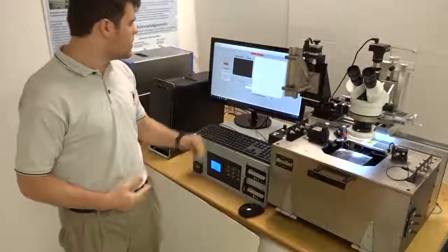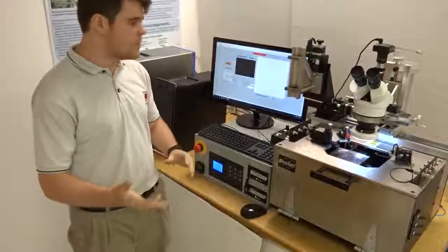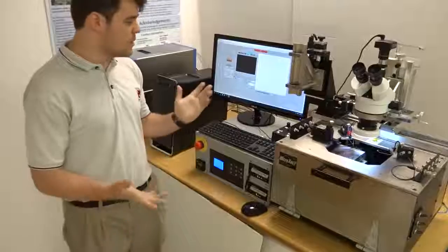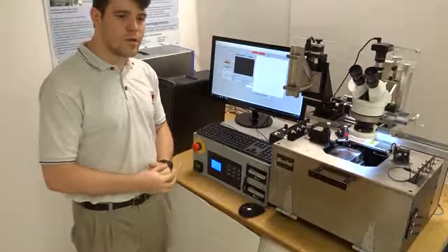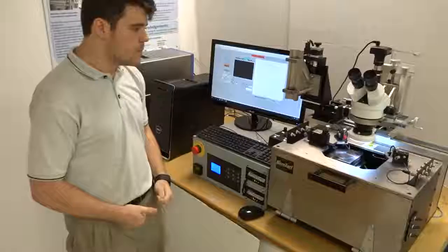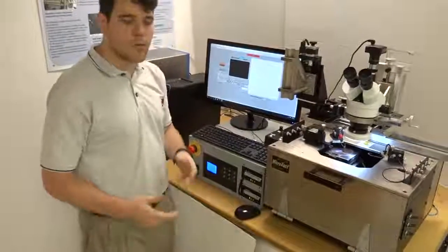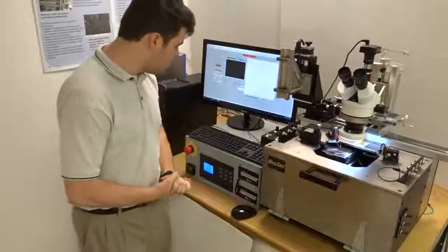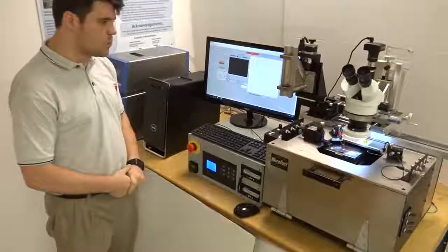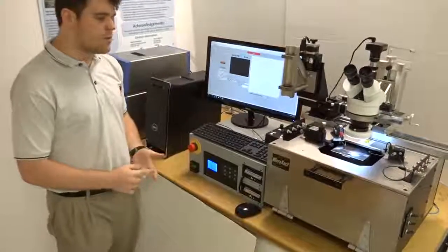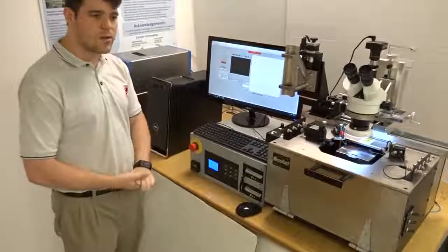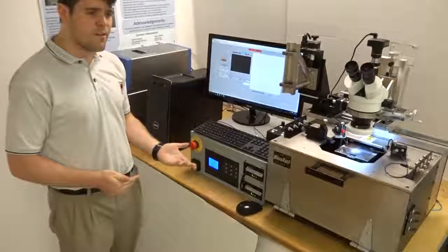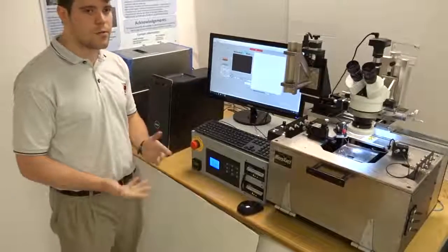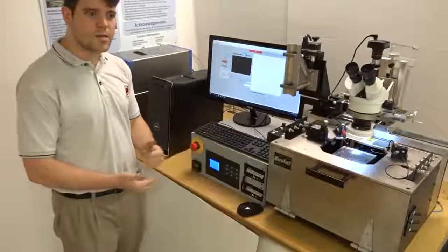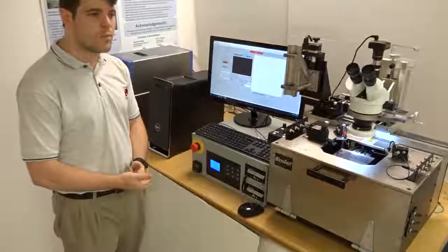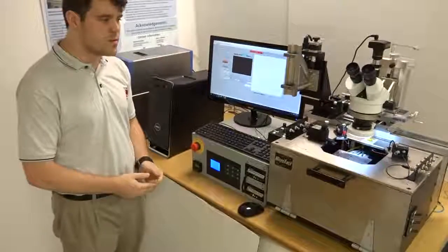We have a camera here that will feed us a high-definition video of what's currently happening, and it will then be able to show us the actual image that we see through this camera. While this is going on, a user can prepare their slides or move whatever they'd like to set up. This control box down here is responsible for ensuring the temperature of our thermal chuck, which can go, in this particular instance, from 5 centigrade up to 80 centigrade. In other instances, we can go even down to cryogenic temperatures if you're interested in this particular process, or up to very high temperatures, up to 600 C or above.